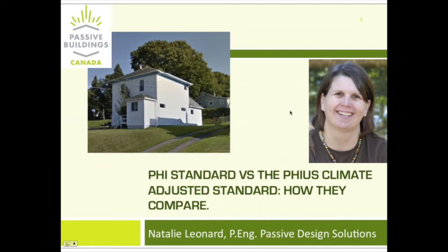This building has been occupied since April. So this is the first winter, and they have monitoring data in the building, but I don't have any of that data yet. But the hot water heat pump was placed in the basement with extra venting into the storage. So I don't expect it'll be affecting comfort based on some of our other decisions, but it's definitely discounted in the energy performance in PHPP with that calculator.